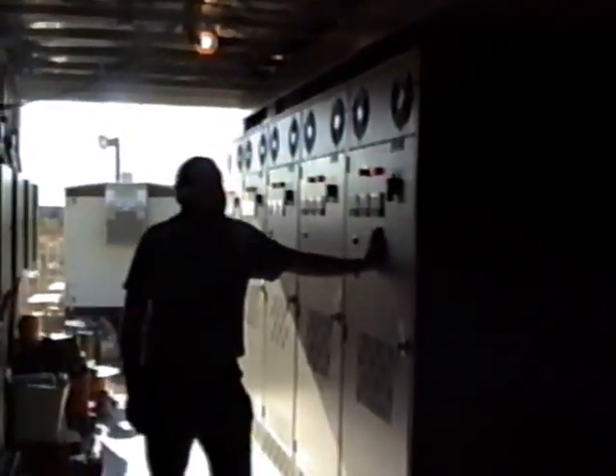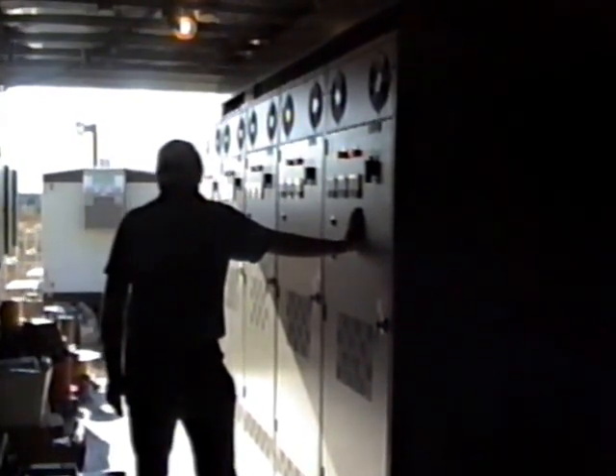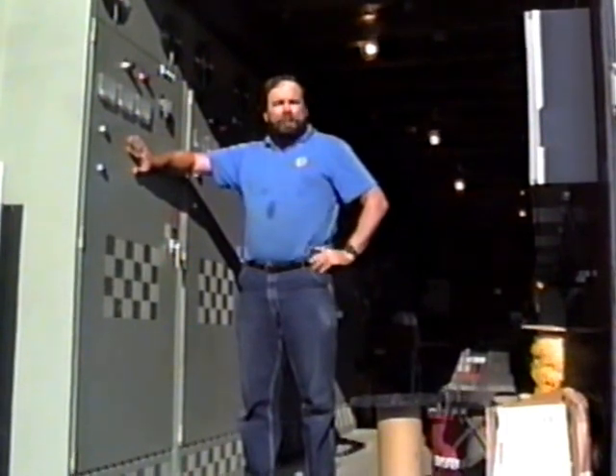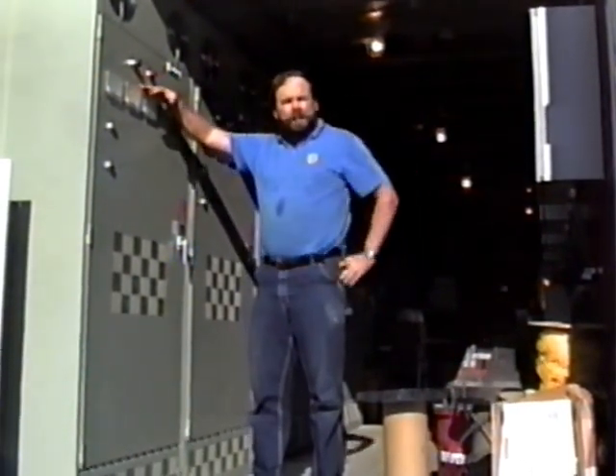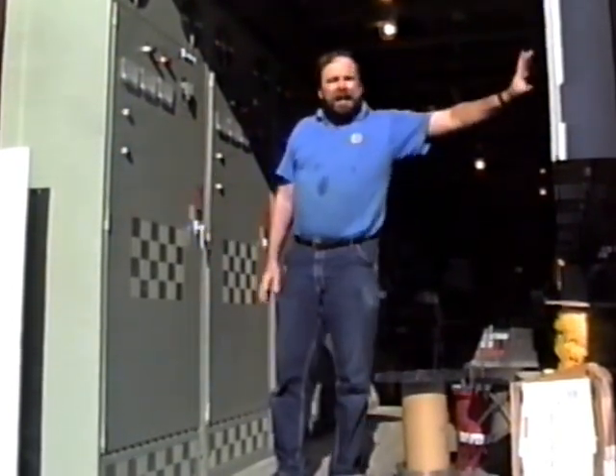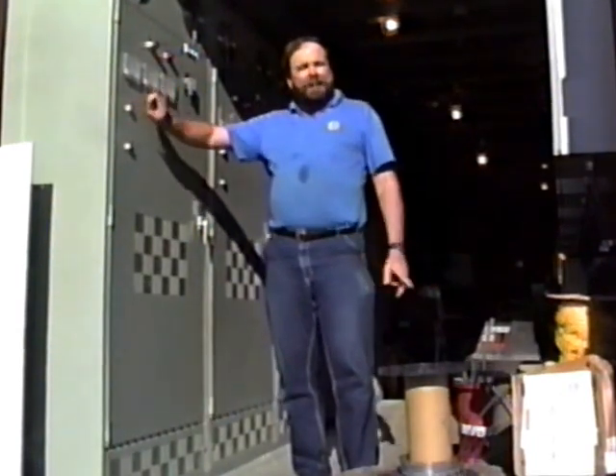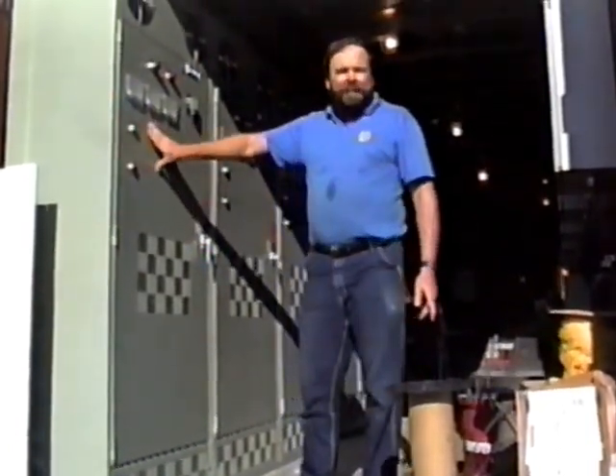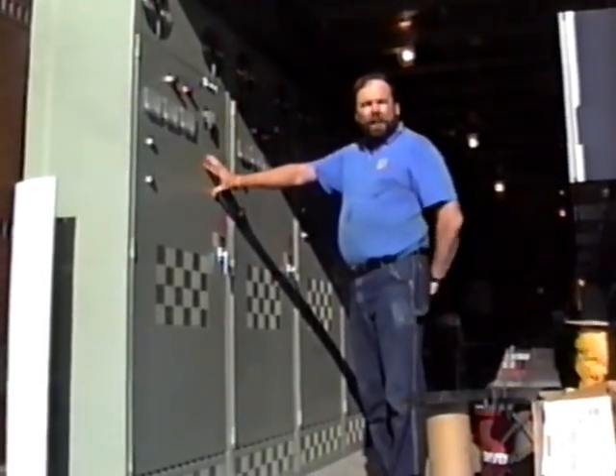Down here is where the connections go to all of the Robicon drives. These are more or less standard 100-horsepower current source inverter drives that we have modified for use on this system. These are the motor drives that put current in the motors to force the car back and forth through the pipes. They started their life as standard induction motor drives, and then at M-Technology we designed new control circuits so they would be able to control the linear synchronous motor used in the ore car. You can hear each one buzzing as the car goes by, and also a thunking sound as the car passes — that's the relays connecting to the next motor. For economy on this prototype, one drive runs every two motors.